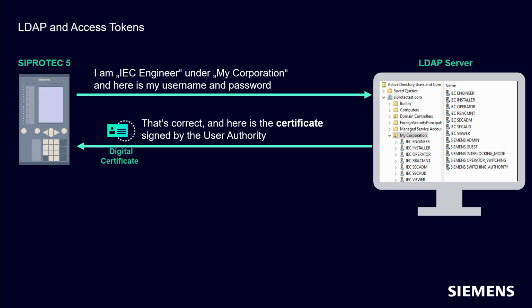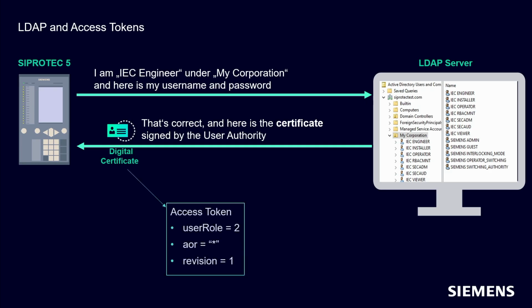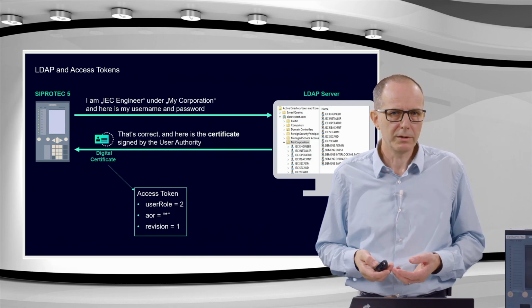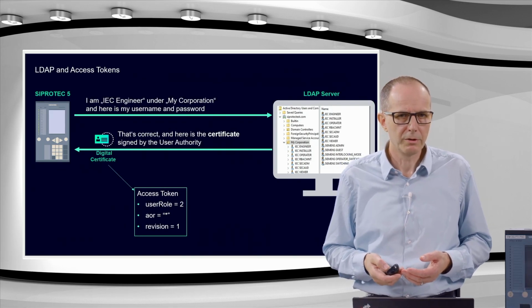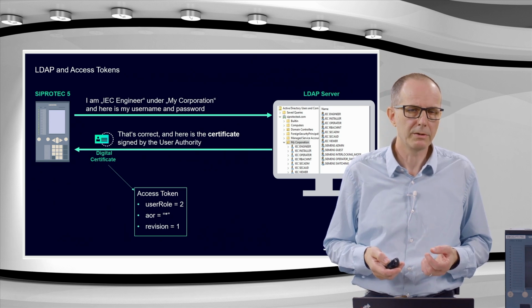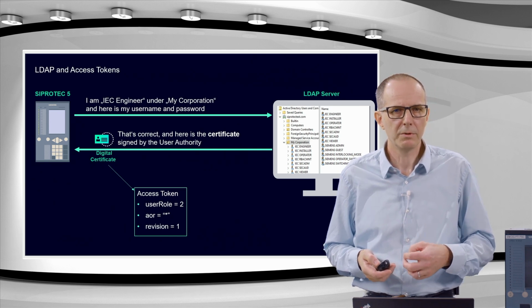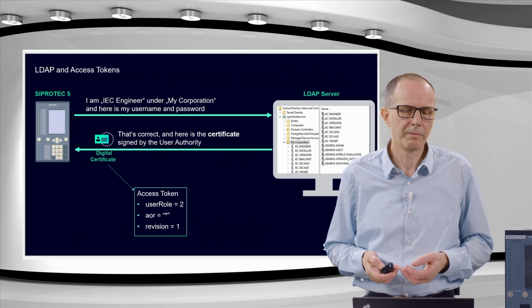To fetch the role information of a user, the client first fetches the user certificate attribute of the user. In this particular property, there should be a binary certificate where the user role details are encoded. According to IEC 62351 extensions, the role details are stored in a list with a minimum of 3 mandatory criteria.